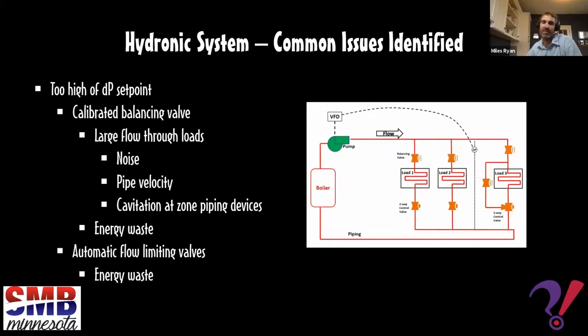All right. Some other issues commonly identified is too high of a differential pressure set point. So the TAB process is typically going to determine what's the appropriate differential pressure set point that the pump should be controlling to. Right? If you have a calibrated balancing valve and you have way too high of a set point, you might have some loads that are having way too much flow going through them. And that can create noise. It can have excessive pipe velocities, which can be damaging to pipes, especially copper pipes. It can also create cavitation at some in-line piping devices, such as strainers and things of that nature. Also, it's a big energy waste.